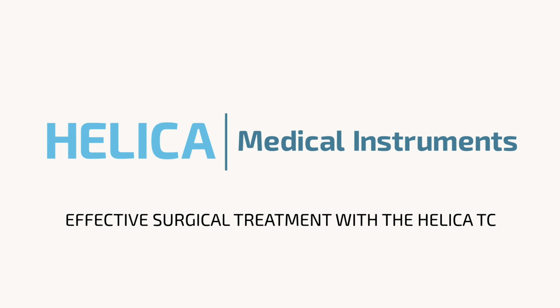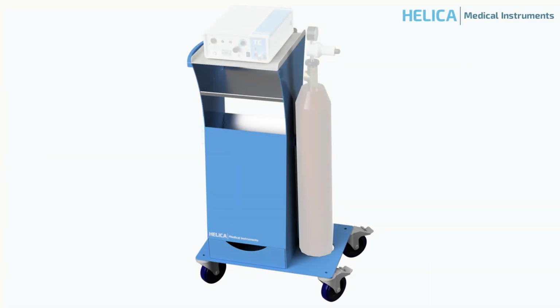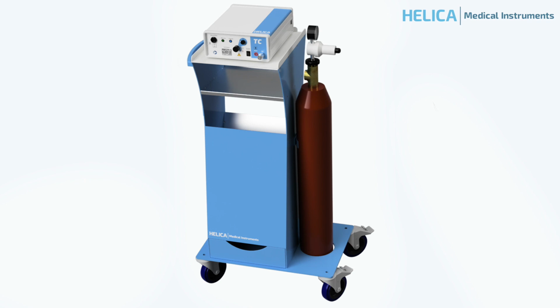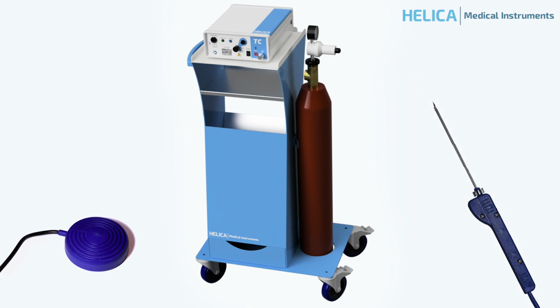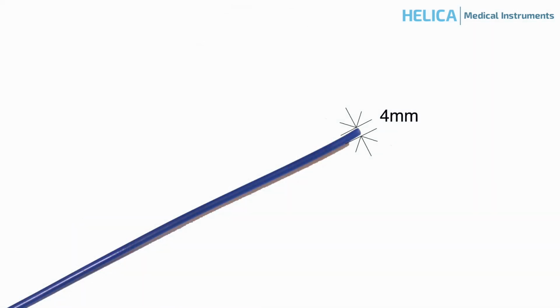The Helica thermal coagulator consists of 5 main components: a purpose-made stand, the instrument, an F-size or equivalent cylinder of medical helium gas with a regulator, a foot switch, and a one-use only probe. Helica probes have an external diameter of 4 mm and therefore will pass through a 5 mm cannula.